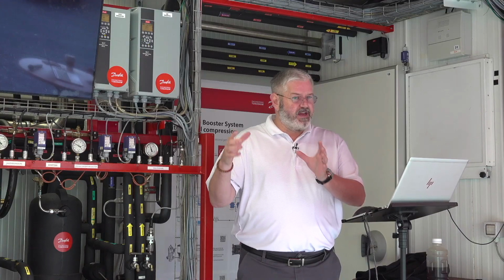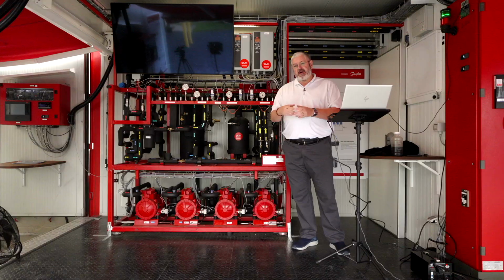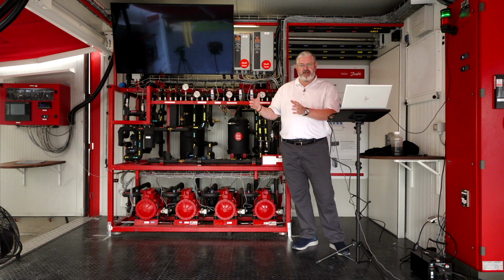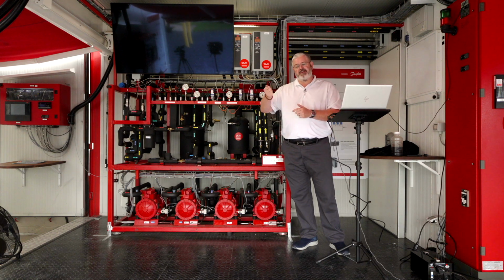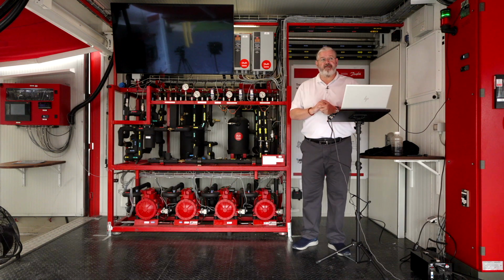If you wanted a cost-effective way, I believe it's underutilized, in my opinion: the single condensing unit that's just meant to handle load in a power outage situation. You've got the heat exchanger that'll deal with whatever pressure's built. It'll keep pressure from building in the flash tank, and it's a very small load to have a generator for. So I think a backup condensing unit with a small generator and a heat exchanger to keep the temperature of the flash tank from reaching the relief valves would be the best option.